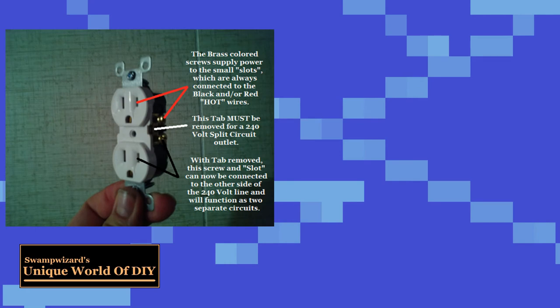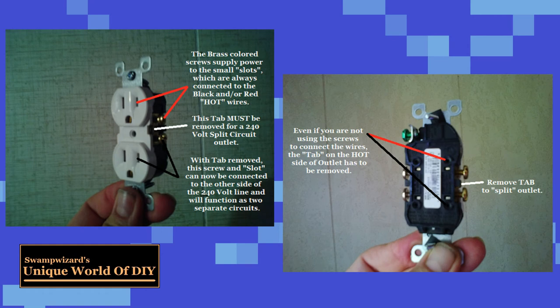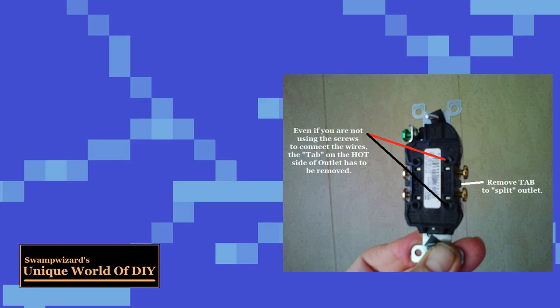But when you're doing any wiring, it's always a good idea to start at the far end and work your way back toward the service panel. When you get to the service panel, of course, you're going to have a double pole breaker for your split circuit outlet. You could also use two single pole breakers if they're side by side, and then you just install a handle tie so that the two of them act as one breaker.